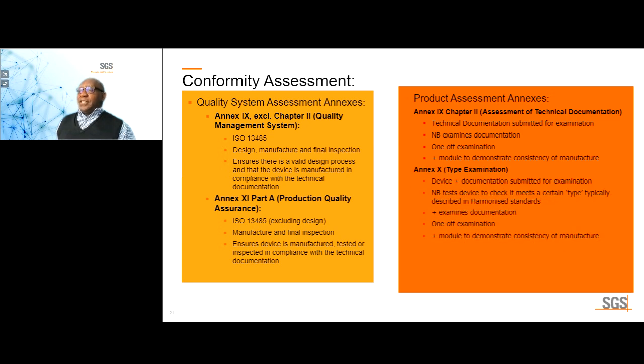Next, under product assessment annexes is Annex 10, type examination, whereby you provide to the notified body a device, your device, plus the technical documentation that you wish to submit. In this case, the notified body then tests the device to check it meets certain types typically described in harmonized standards, conducts an examination of the documentation. Again, it's a one-off examination and has to be combined with another module to demonstrate consistency of manufacture. I need to point something out here. Unlike Annex 9, Chapter 2, where you're only providing a technical documentation, with Annex 10, keep in mind, you also have to provide your device, which the notified body must test.